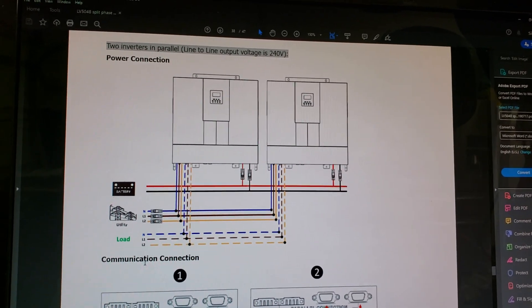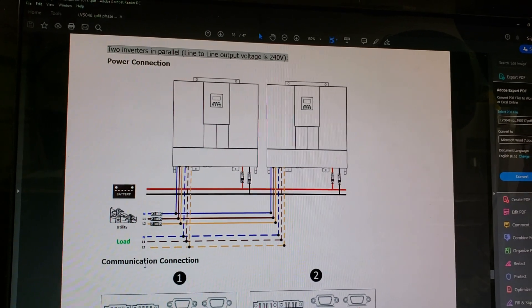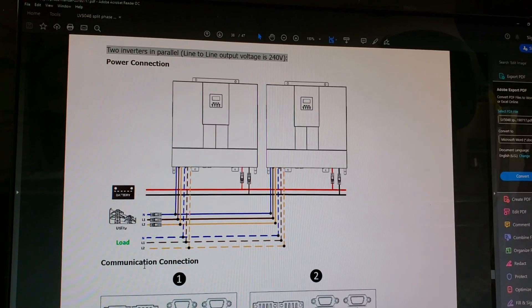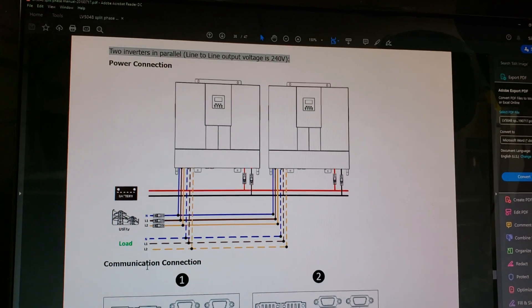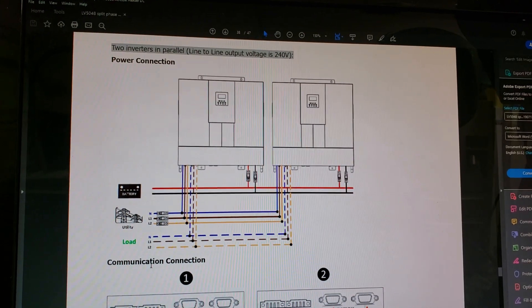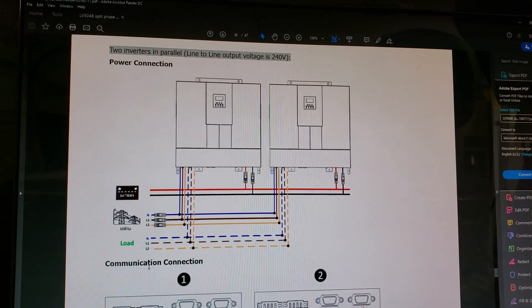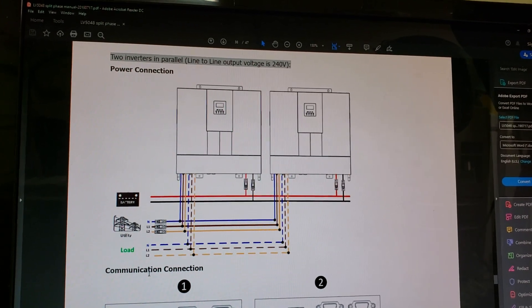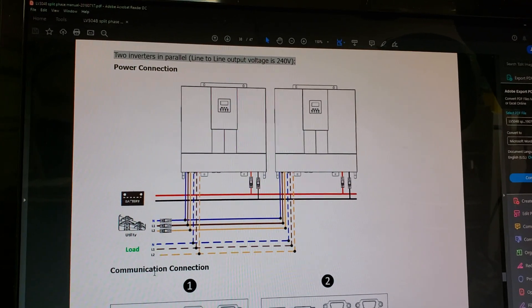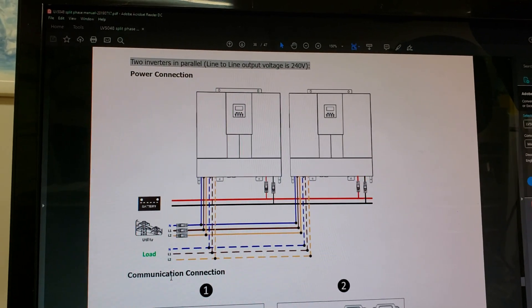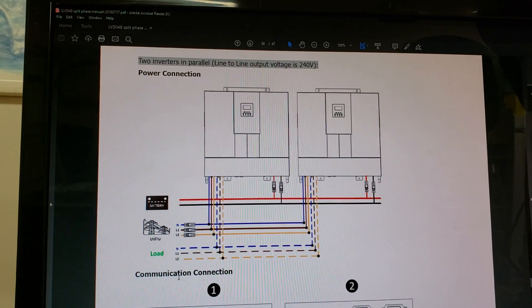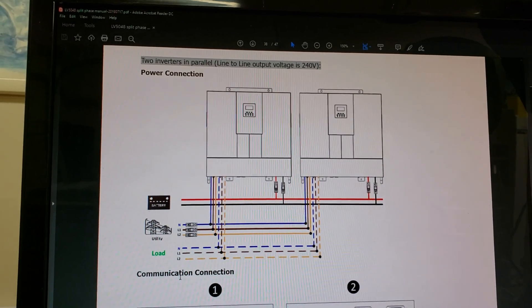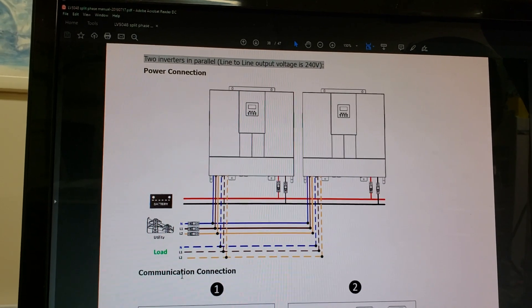For batteries, if you have one pack or two pack or three pack, doesn't matter - they both have to be hooked up to both units at the same time. Even a single 48 volt battery pack needs to be hooked up to both positive and both negative terminals of each inverter. Same thing goes for the supply from utility and same for the output off the inverters. All lines have to be in parallel.